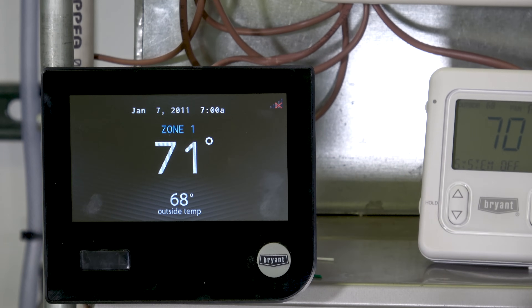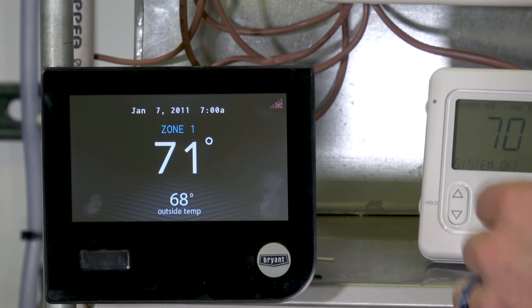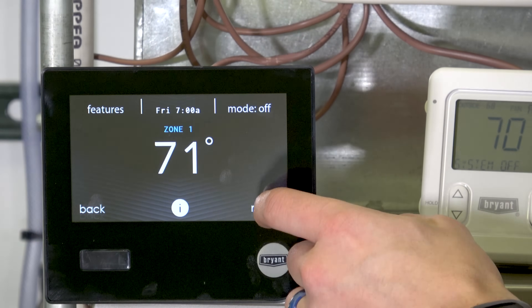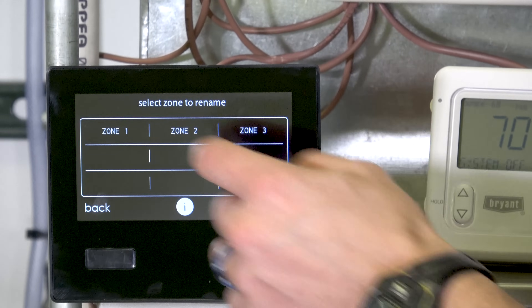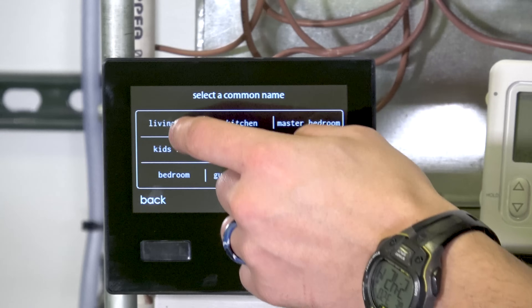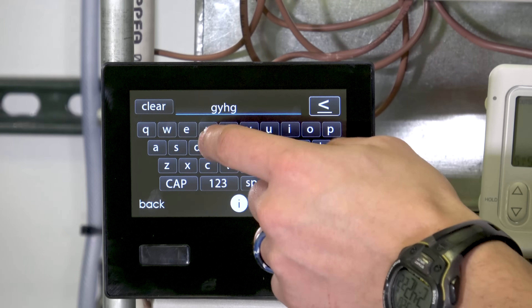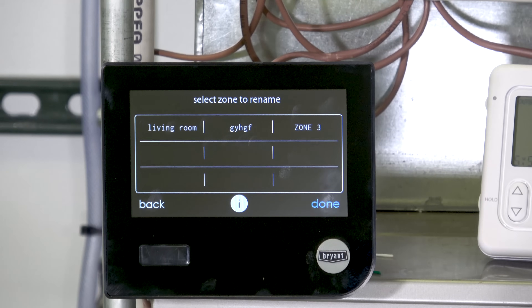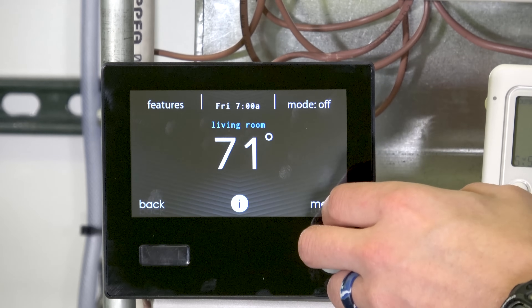The system is ready to operate, but there are two more things to show: naming the zones and adjusting airflows. For naming, scroll down in the menu to zone names, click any one, and pick from a drop-down list — like 'living room' — or type in a custom name. It's a good idea to name zones even as the installer; 'southwest bedroom' is meaningful, but 'zone three' won't mean anything later. We can also go into advanced service settings to configure extra zoning options like CFM and airflow adjustments.